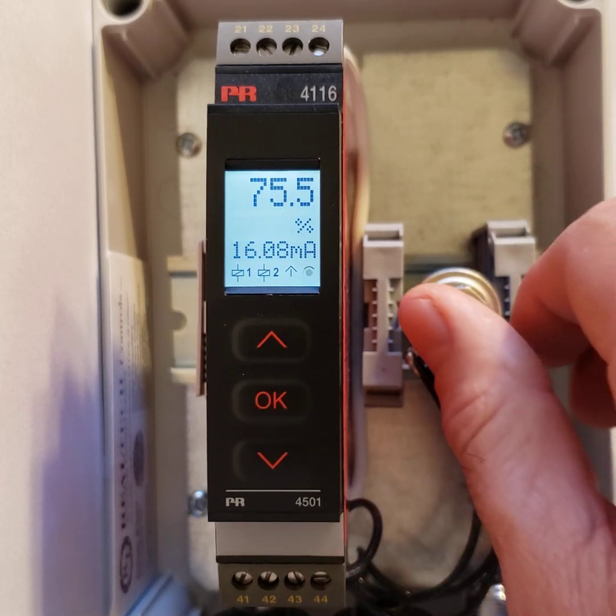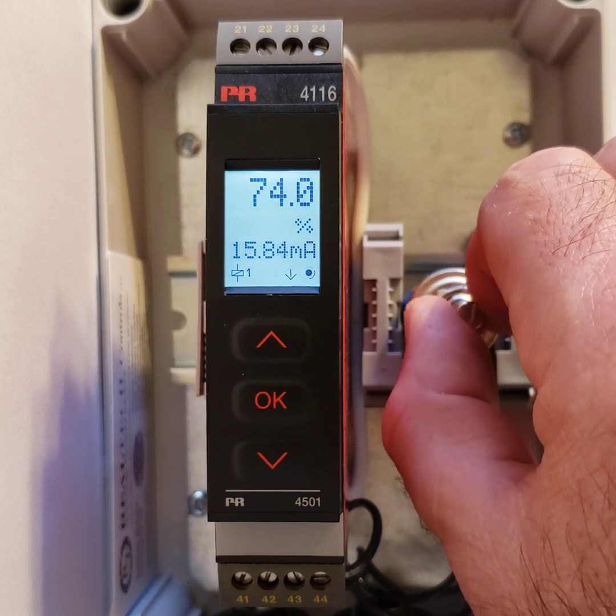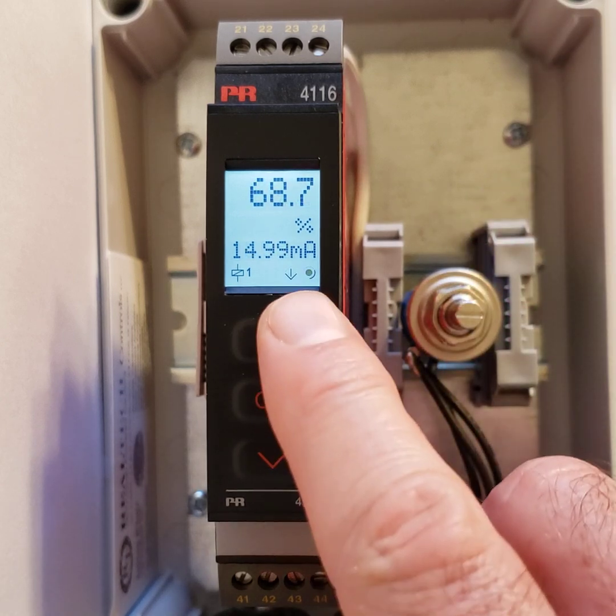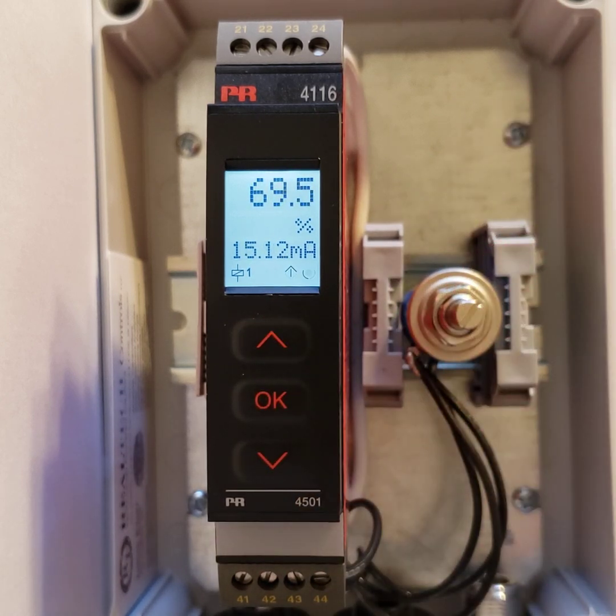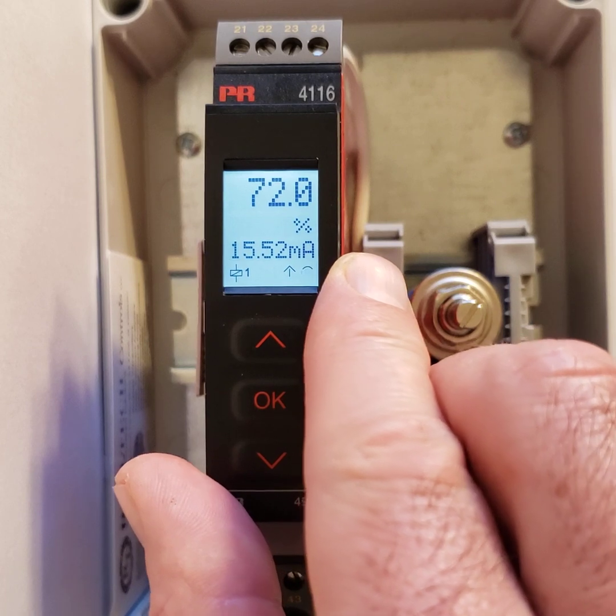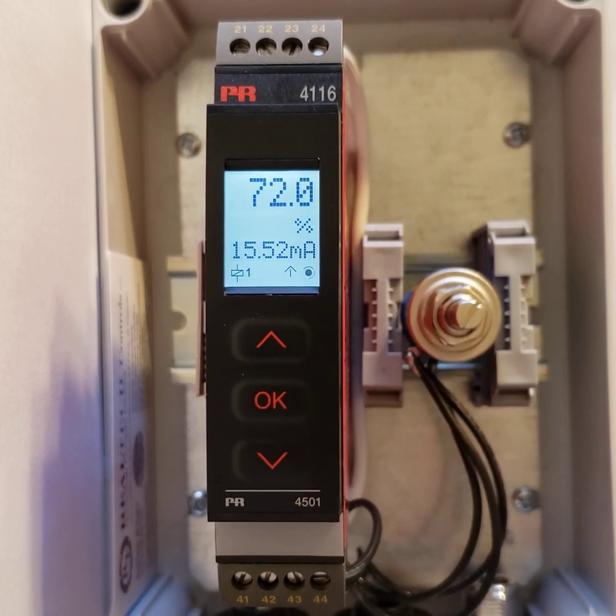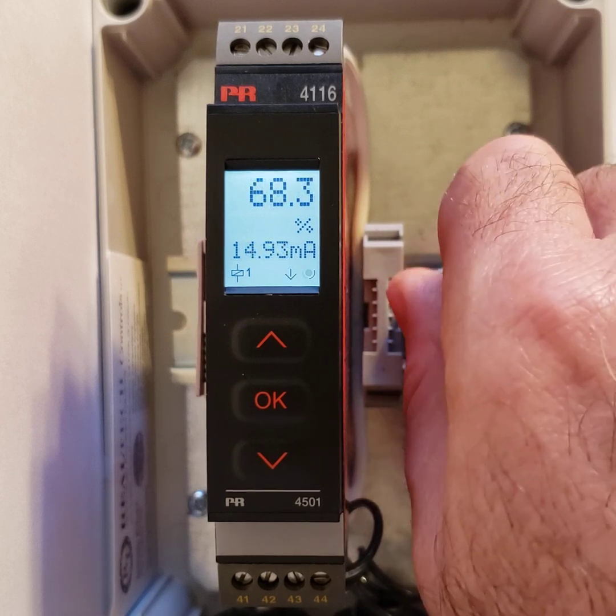The up and down arrow is the general trend of the device. So if I'm going lower, it shows you my process is going down. If I go up, it shows you my process is trending up. And the little heartbeat on the side there is to show you that the 4501 display is communicating with a 4116 transmitter. Okay, I'm just going to turn off all relays for now.